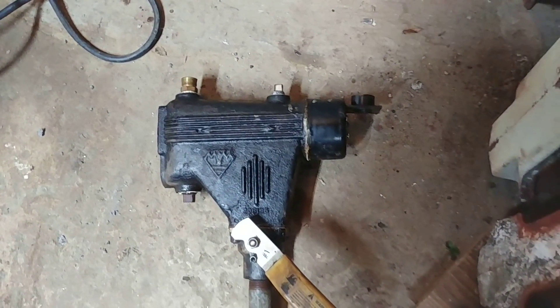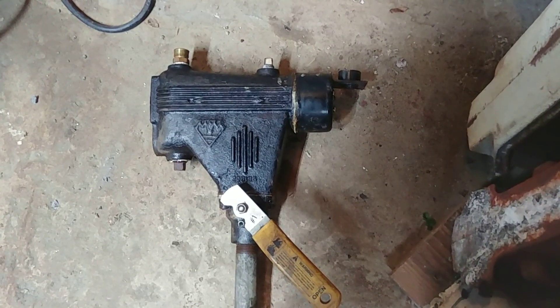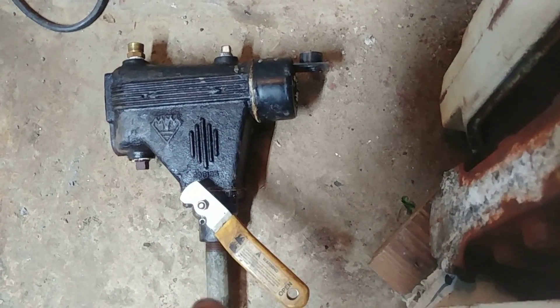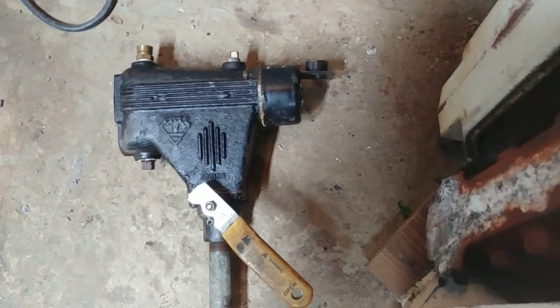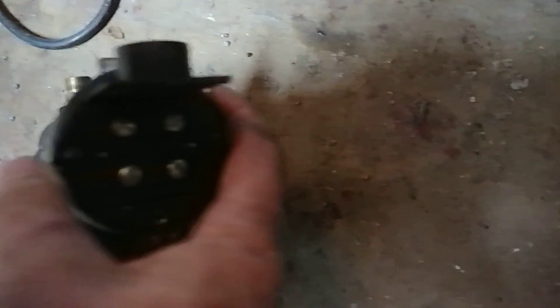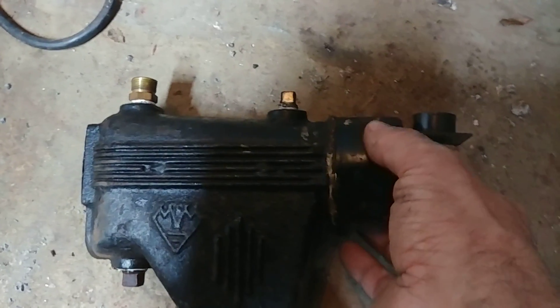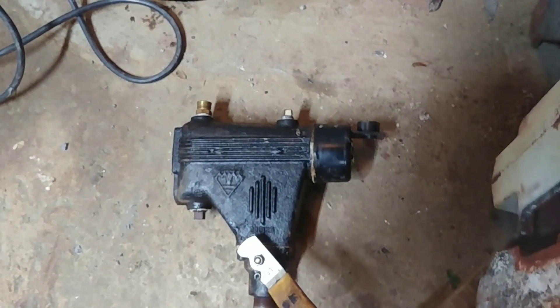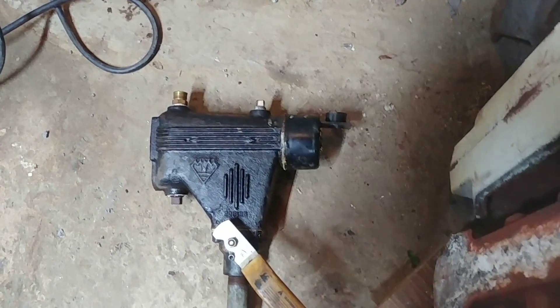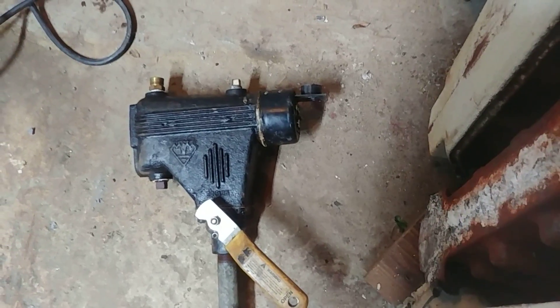You're supposed to blow it down, and most people do. What should happen is you should fire the boiler manually and exercise the handle — open the handle, allow the water to drain, and make sure the float drops and shuts off the burner. The burner connections are on these two terminals here. The bottom two terminals should then turn on the water feed, but the water feed is not really a safety device. The low water cutoff is, and that should be done at least once a week during the heating season. You've got to make sure that the float moves and turns off the burner.